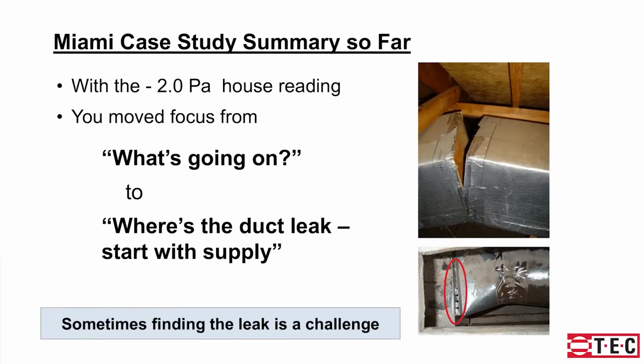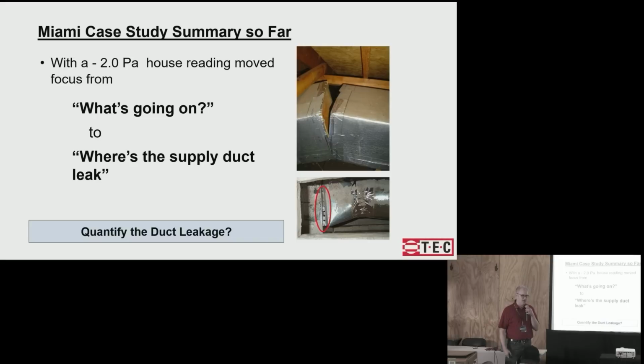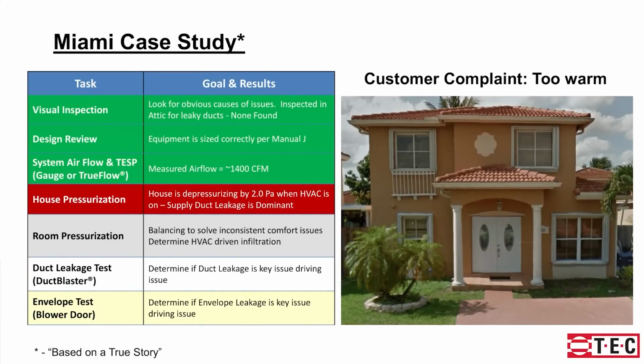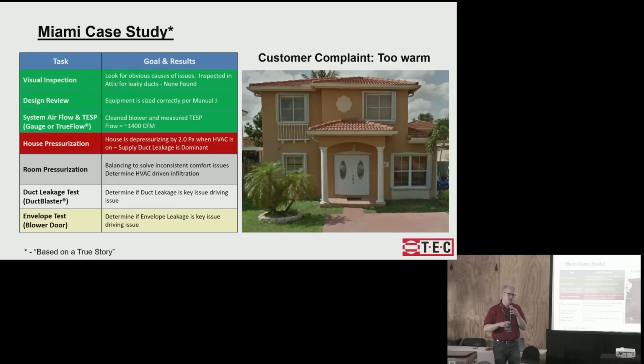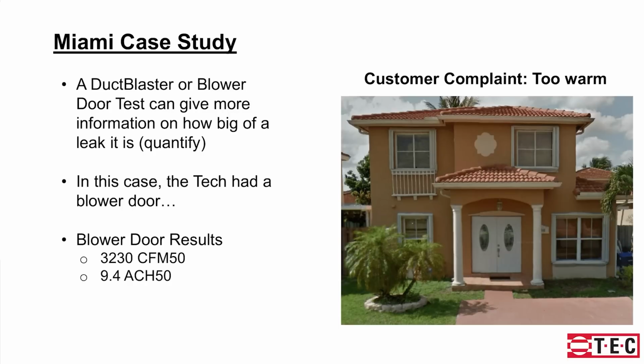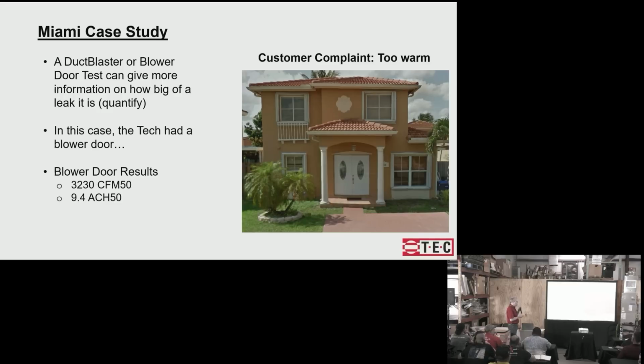Okay. So far, we know there's supply duct leakage, but like I said, the technician went in the attic and did not see any major problems in the ducts, and we're leaking quite a bit. We'll talk through how you find out how much you're leaking, but we know there's a supply leak, we just don't know where it is. Okay, so the next step would be room pressurization. That's a very good diagnostic, but in this case, we're not talking about certain rooms being uncomfortable. So that test is really not necessary if the problem is the system's not keeping up, even with all the doors open in the living space. We know there's a problem, minus 2 pascals of depressurization, but we don't know how much.